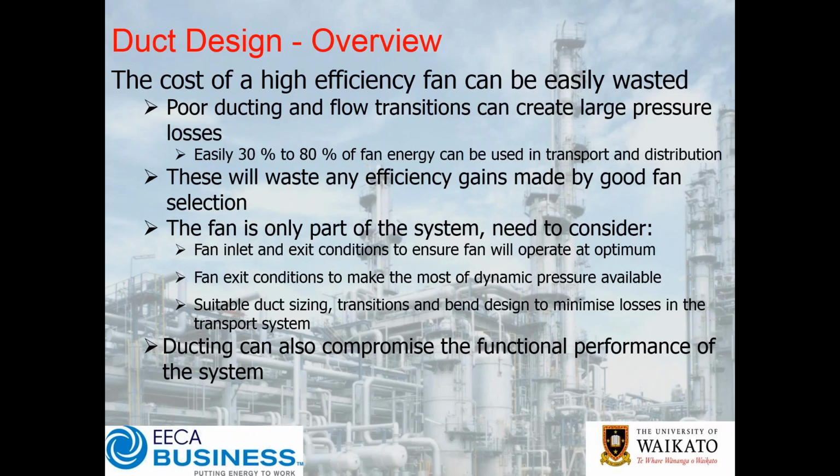Similarly, if you've got a really bad outlet to the fan or really poor duct transition from there to where the air's got to go, might be that the fan's in a really tight spot in the factory, and you have to compromise on the duct design. If you don't get that duct design right, once again you can foul the whole nest.